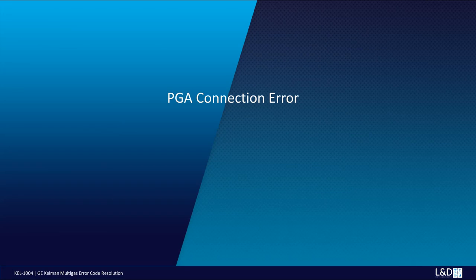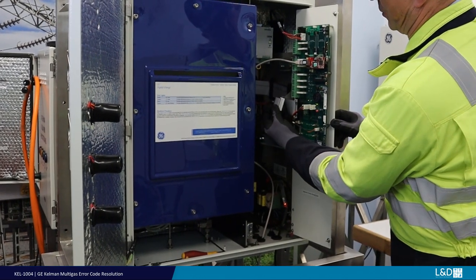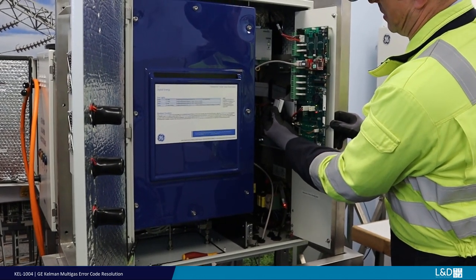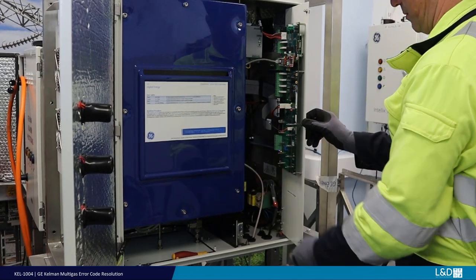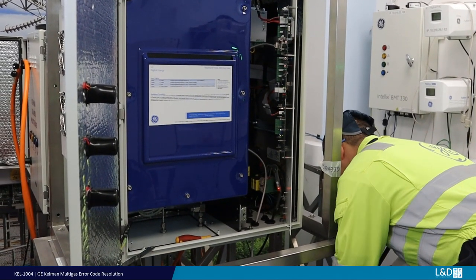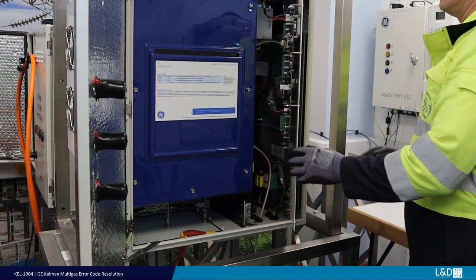PGA connection error. This may be due to the main communication cable disconnection or loosening and may be checked and rectified as shown. Safely power off the monitor and check the security and fitment of the main ribbon cables, looms, or with DGA900 the PGA, for presence, connection and tightness.